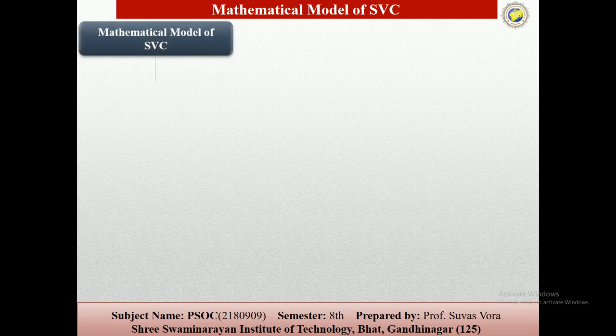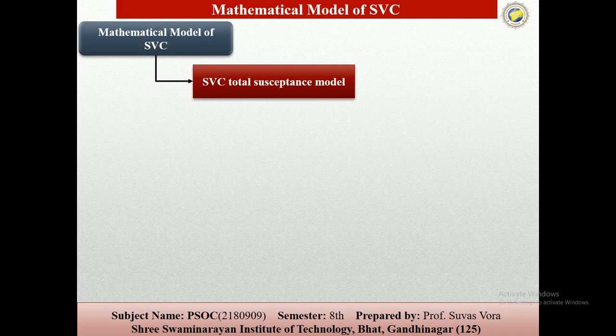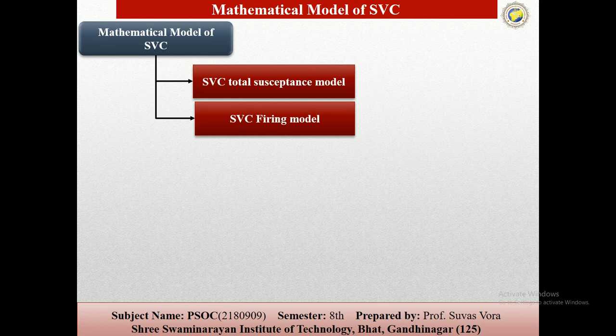Now we can talk about the mathematical models. The mathematical model is used to control the voltage of the bus by controlling its equivalent reactance. Basically it consists of the fixed capacitors and the thyristor controlled reactors. There are two types of SVC models, the SVC total susceptance model and the SVC firing angle model.